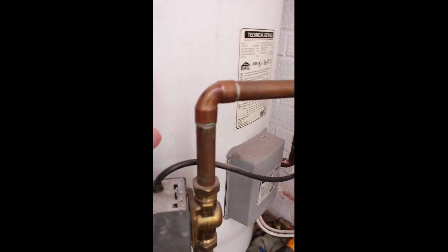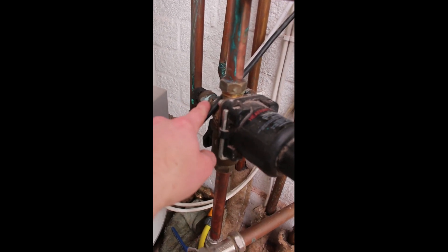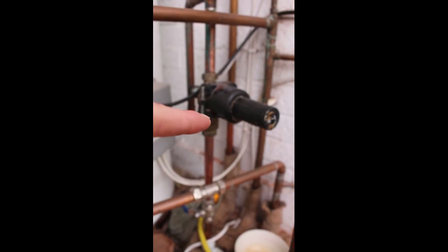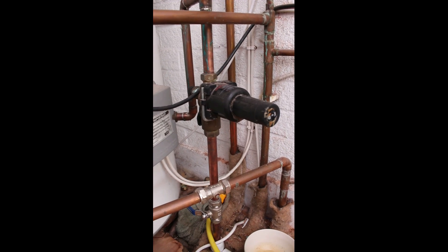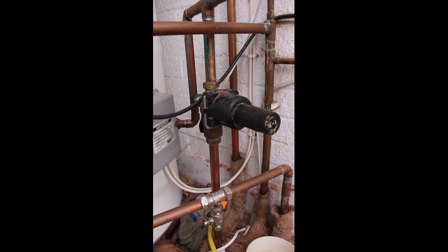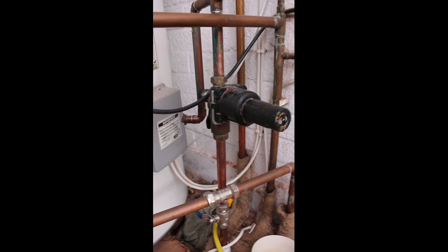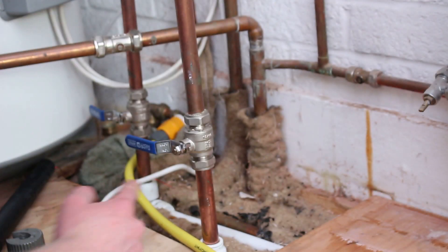Different manufacturers of unvented cylinders may have slightly different pressures at which their valves discharge. This valve here — the cold water inlet balancing valve — sets the pressure within the unvented cylinder at 3 bar. On this particular Megaflo model it happens to be 3.5 bar.